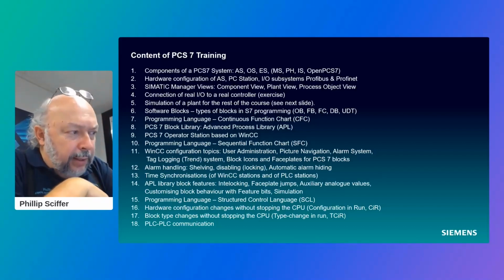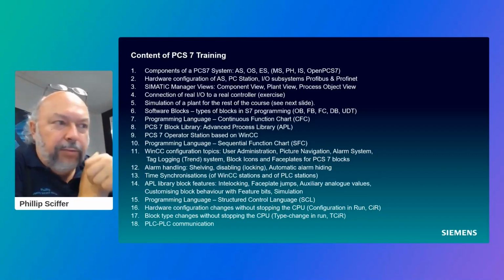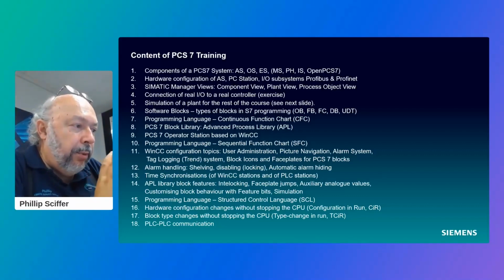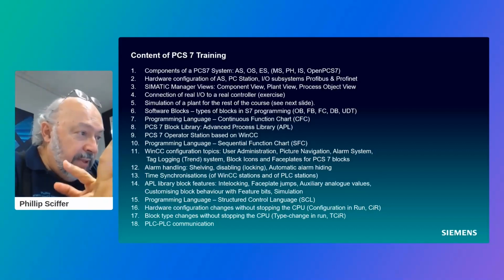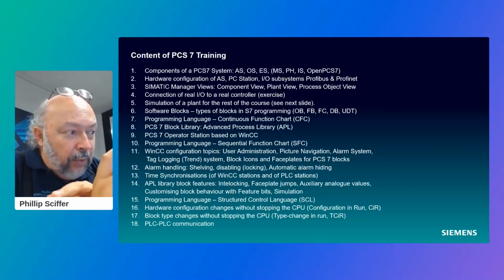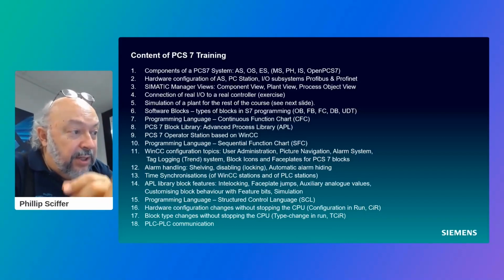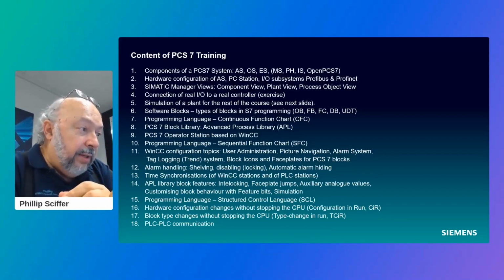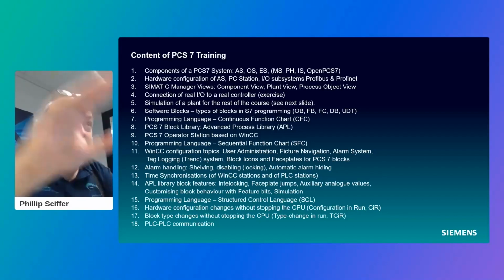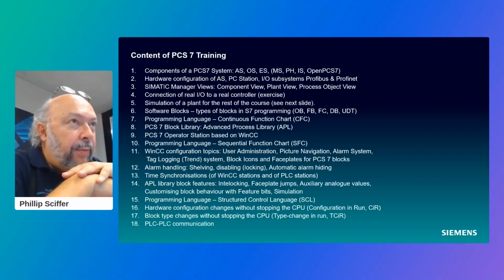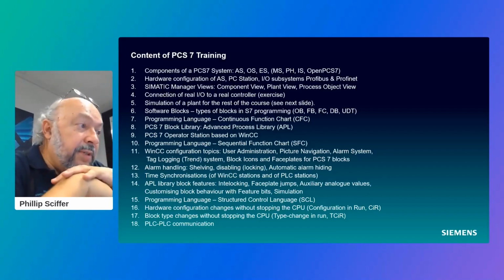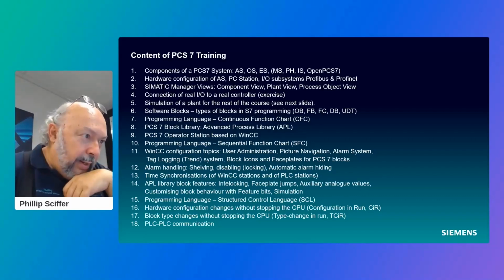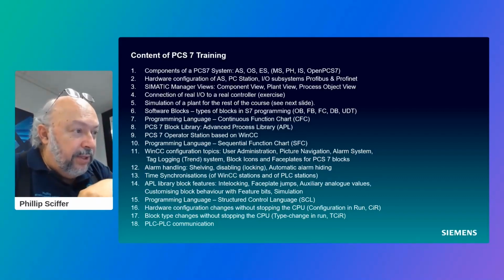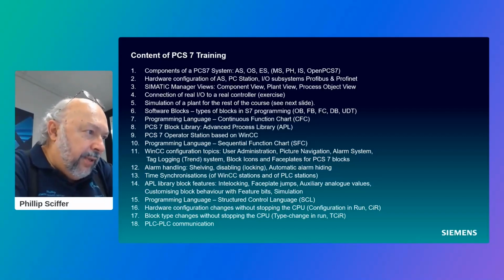We do a topic on alarm handling, things like shelving alarms, so that nuisance alarms don't bother the operator, disabling or locking alarms, and configuring automatic hiding of alarms based on plant operating states. We look at time synchronization of WinCC stations and of the PLCs. So if you've got a system that's got an HMI station and several clients, it's necessary to have the clocks synchronized so that when you acknowledge an alarm on one station, the time is accurate and comparable to the times that the alarm happened on the other station. So WinCC can do that for us.